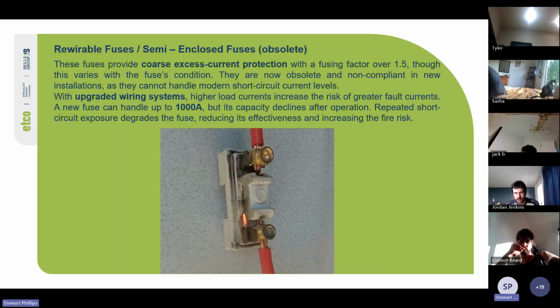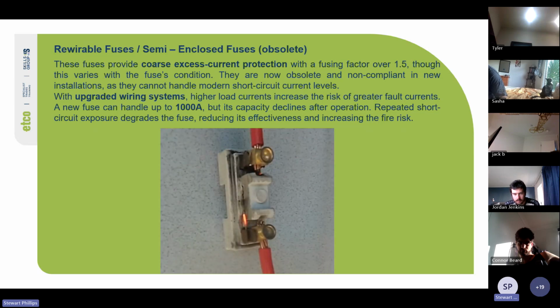Yep, so only rated at 1,000 amps, but the majority of the time in new installations, when you're doing your fault loop impedance testing, you're routinely getting above 1,000 amps. So it was 1,000 amps new, maybe 800 after a few times exploding, and then 700. You can see how these fuses are no longer safe or are obsolete.